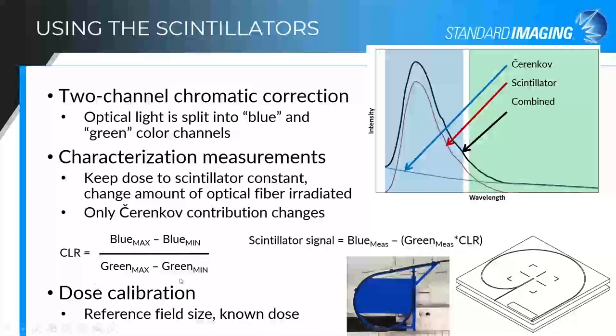If you'd like to apply a dose calibration to your device, you give it a known dose in your reference field size, and that becomes essentially a unit conversion — a constant multiplied by the corrected signal to give output in terms of dose.